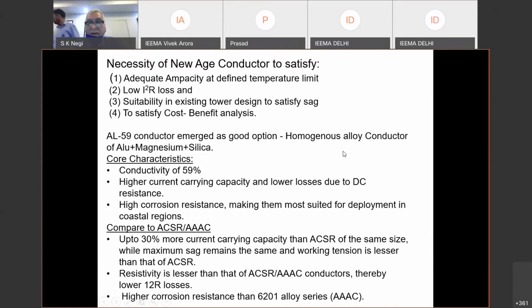This is a homogeneous alloy conductor, aluminum, magnesium, and silica alloys. And its core characteristics are conductivity of 59% of the IACS, and that is International Annealed Copper Standard. And all of you must be knowing that when we talk of a conductor, we compare with this, we take that as a reference, and then we tell the conductivity.